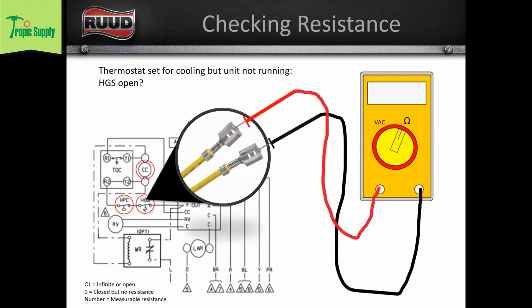Isn't continuity easier for checking pressure switches? I mean, it can be. It really just depends on how I learned to use my meter to just look at the resistance settings. But continuity will tell you because it'll beep if it's open or closed. What it won't tell you though is how much. Well, some meters will read out your ohm reading at the same time as beeping, and that's fine. You just want to look and see how much resistance you have, right? Because you have a switch that's been opening and closing, it could have built up some resistance, and it could be pitting. You could have pitted contacts in there, and that could be one reason that your relay is chattering, or the linkage of your contactor is chattering, because you've got a voltage drop across that switch.